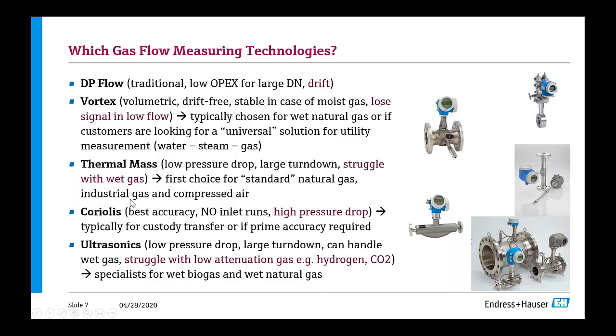Then here we have thermal mass flow meters. They come with a low pressure drop, have a large turn down, but they struggle with wet gas. And they are the first choice for standard natural gas, I would say, for industrial gases and for compressed air. Then Coriolis meters, they come with the best accuracy and they don't require any inlet runs. That's a big benefit of this technology. However, they have a high pressure drop. So this is why in some gas applications you won't use them.